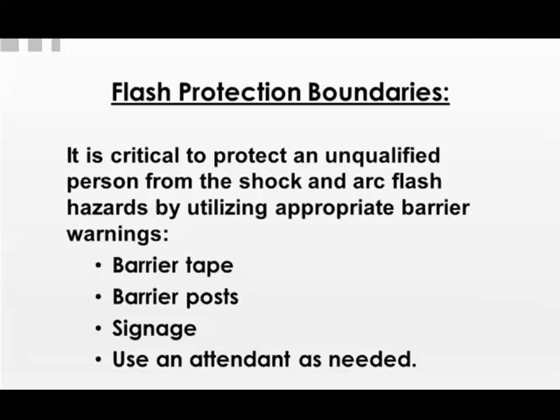Flash protection boundaries. So it is critical to protect an unqualified person from a shock and arc flash hazard by utilizing appropriate barrier warnings. Ideally, you want the area where any arc flash can occur to be cordoned off, physically separated off, ideally controlled and in a locked environment, like let's say an MCC room or something like that. But if it can't be, because of the physical layout, you want barrier tape up, you want barrier posts, certainly you want signage.